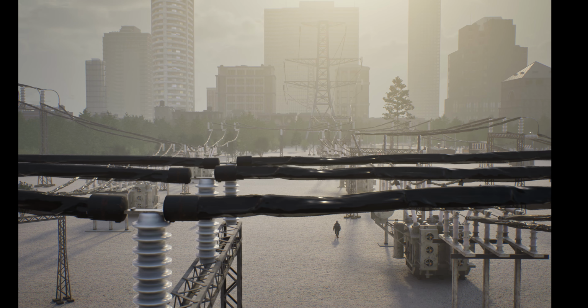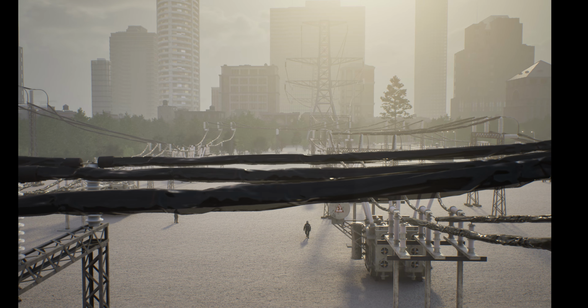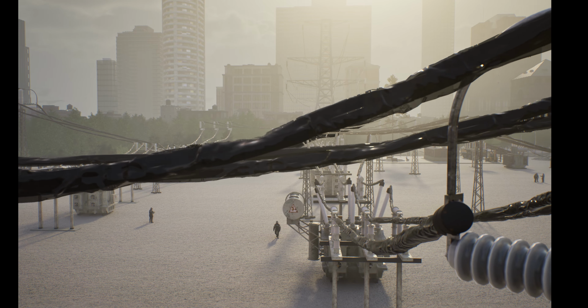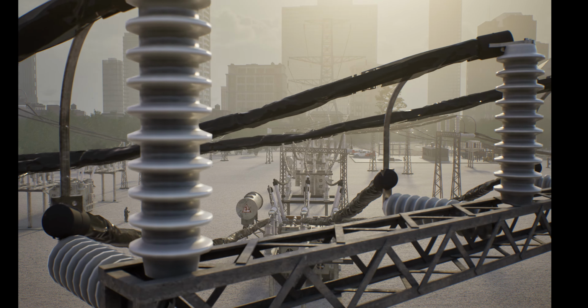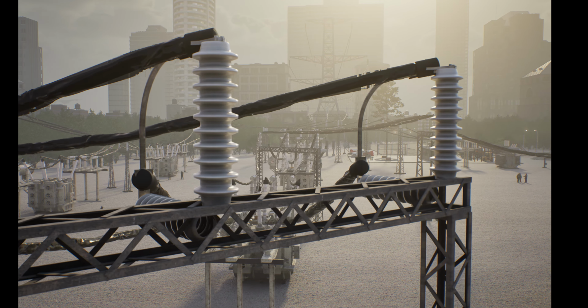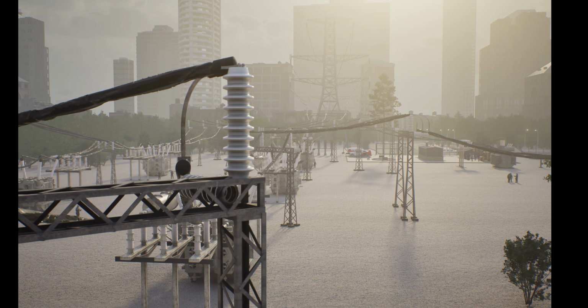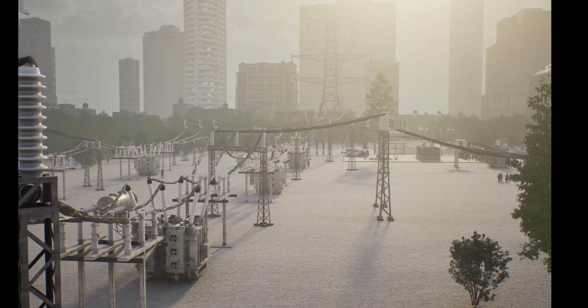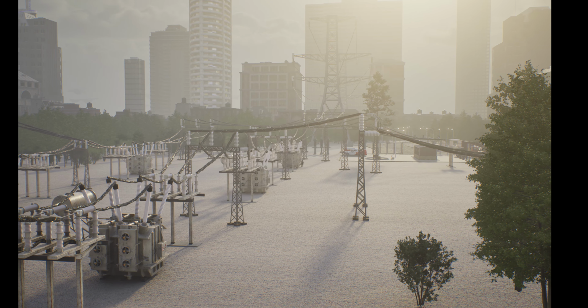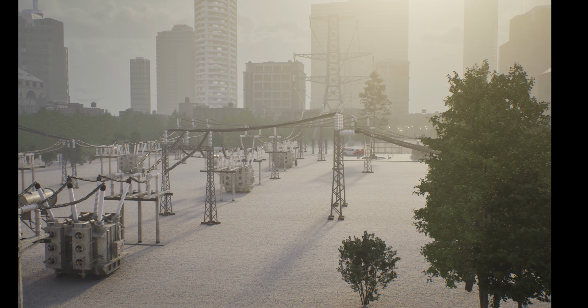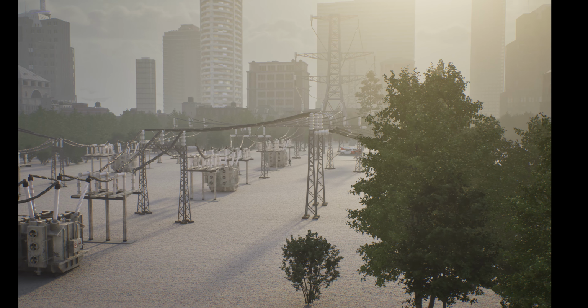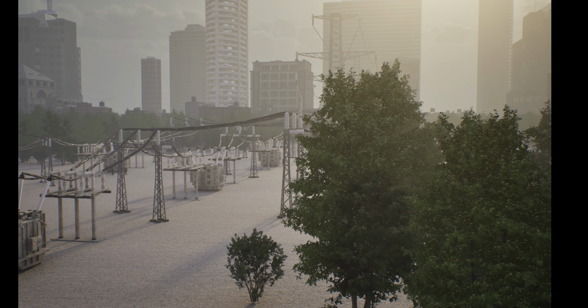Before entering a substation, it's important to understand one core principle. Always assume all conductors and equipment are energized unless formally proven otherwise. Both OSHA and NFPA 70E require equipment to be treated as energized until it has been properly de-energized, locked out, tested, and grounded.